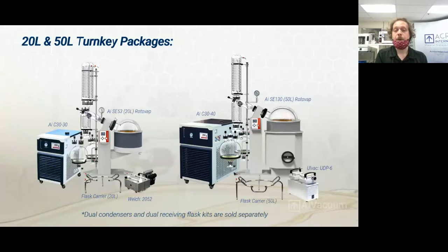And we have peristaltic pumps for all that draining as well to make that easier and hands-free for safety as well. And then each rotary evaporator will also include a boil cap. Basically, it's a steam channel so that you can duct out the steam and or get it away from your operators that are using the rotary evaporator.